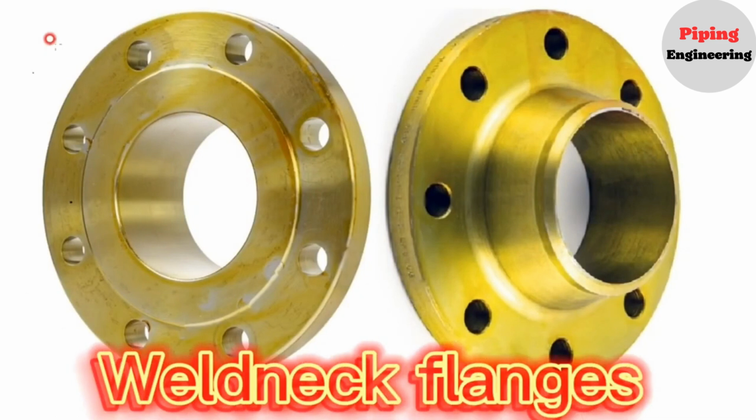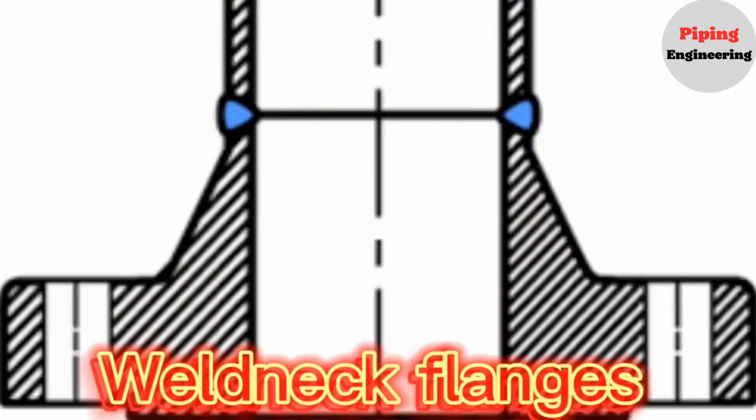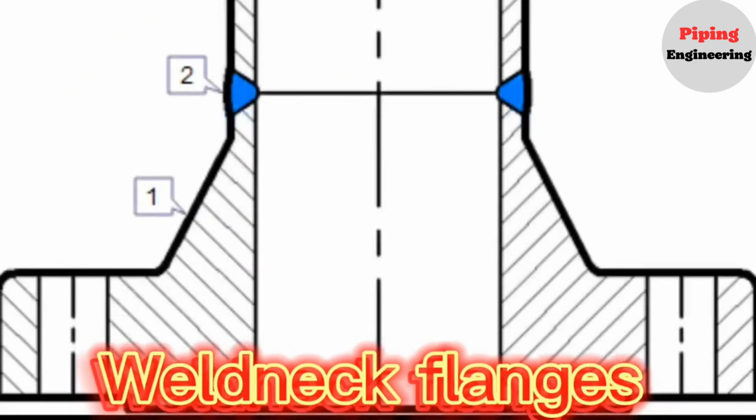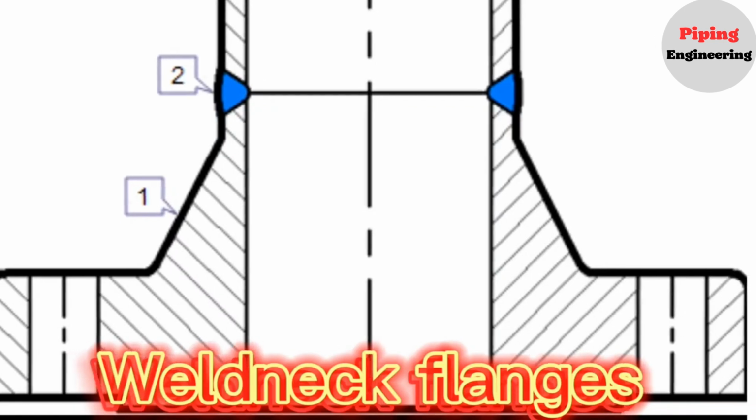What is a weld neck flange? It is very easy to identify a weld neck flange from the appearance because it has a high, tapered hub like a neck. Weld neck flange is welded to pipe with full penetration weld. It also has the effect of dispersing pressure, making the pipe less deformable. This flange kind is used, generally, in high-pressure and also high/low temperature applications that call for an unrestricted flow of the fluid conveyed by the piping system.